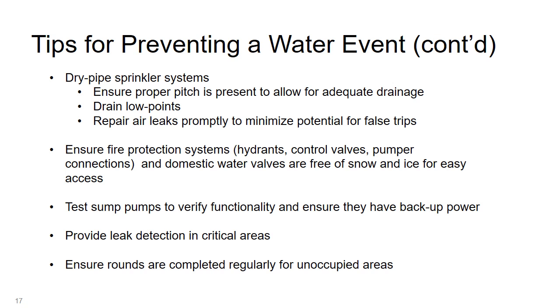Sprinkler systems are usually installed in heated areas of buildings. However, when they're installed in colder areas such as loading docks or parking ramps, a dry system may be used. Here are some of the things to keep in mind for dry pipe sprinkler systems to minimize the potential for freeze-ups. The goal here is to minimize water being trapped in low points of the piping system where it could freeze and cause a failure. Sump pumps are also critical to remove water from low or below grade spaces.